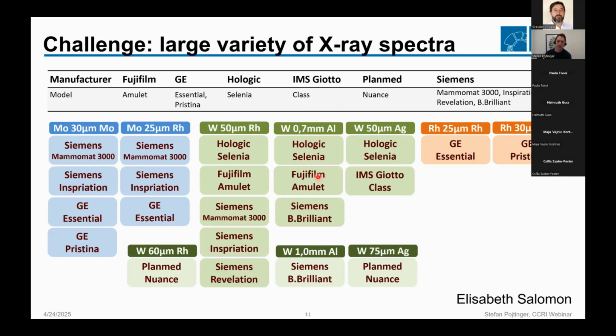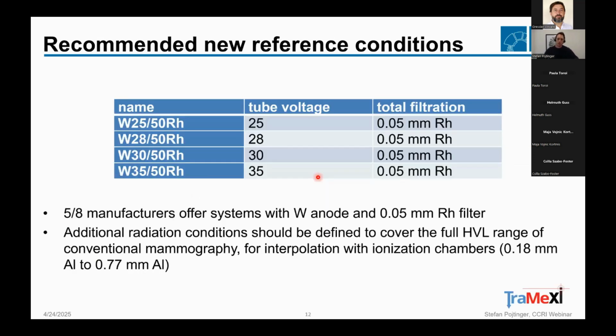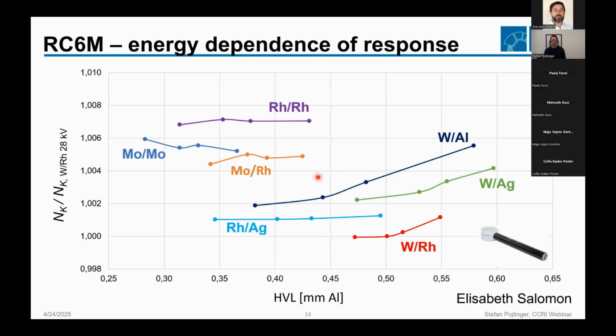What we found when looking at all of the data in our list is that there is at least a most common combination. We found that 5 of 8 manufacturers of mammography devices have the combination tungsten with 50 micrometers of rhodium. So our suggestion for IEC would be, of course, we cannot standardize all of the combinations, but maybe include the most common combination, and from our perspective that is tungsten rhodium, as you can see here. In addition, we would also suggest having one anode filter combination you can use to cover the whole HVL range to do some kind of interpolation. But as you can see here, that can be challenging, depending on the uncertainty we are looking at.